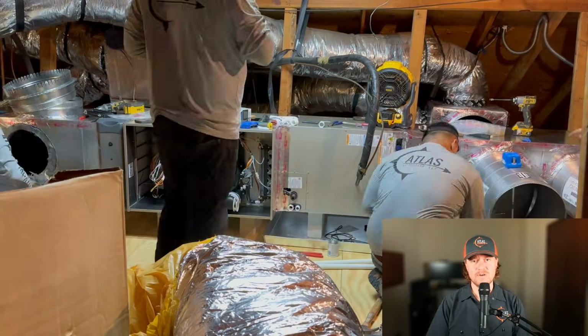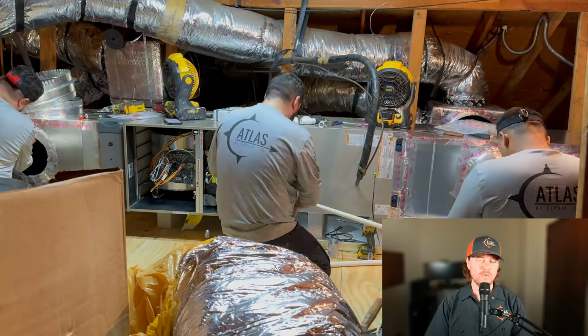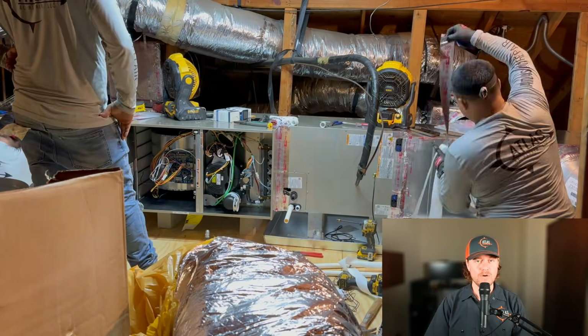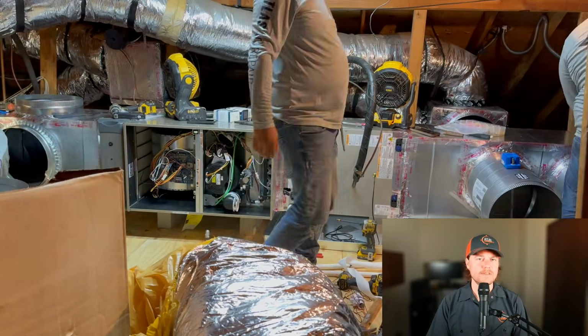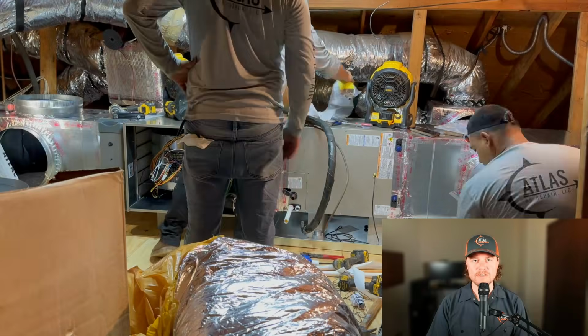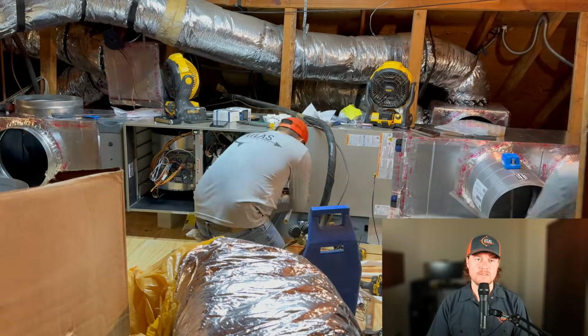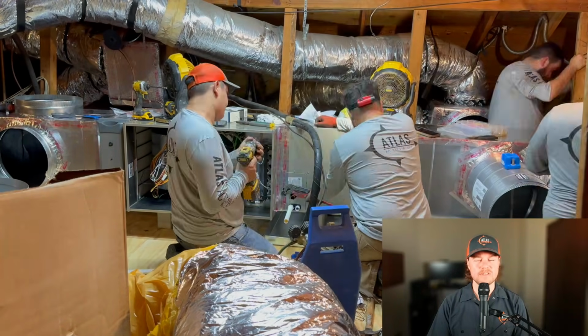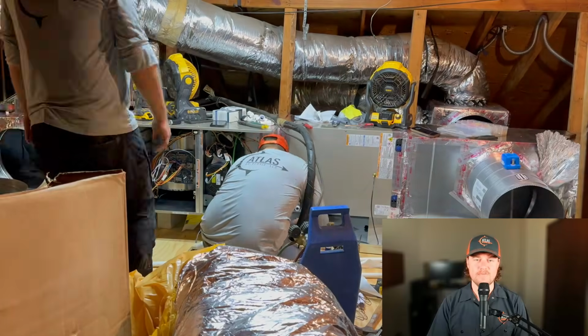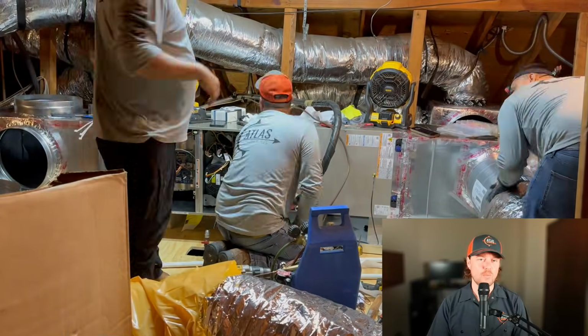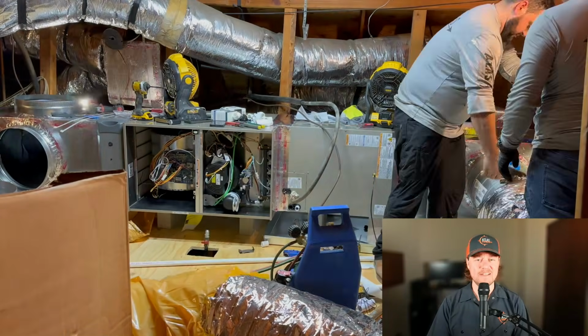Both non-zone and zone have their pros and cons. For my house and the way I run the system, there ends up being more pros than cons. If you end up putting one of these systems on your house, I do have a couple recommendations. Keep in mind that this is only one system. Because of that, I would not have one zone set up for cooling mode and another zone set for heating. The system can only perform one task at a time, and this can end up freaking it out.